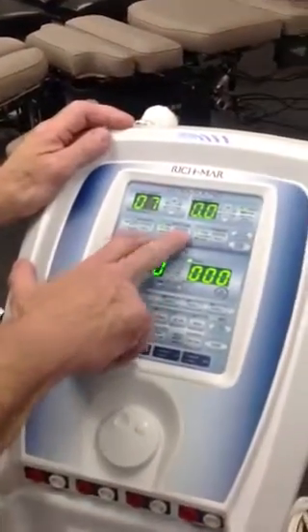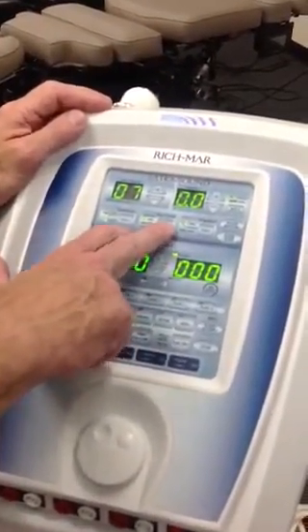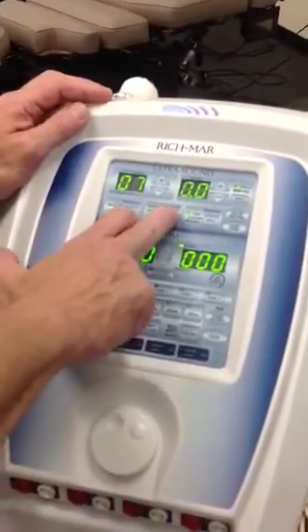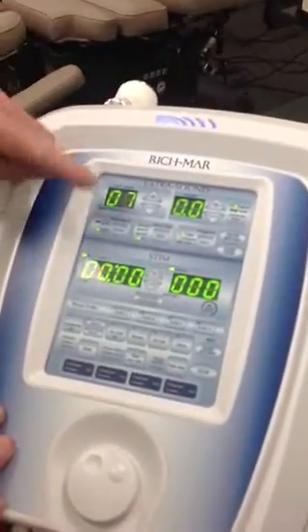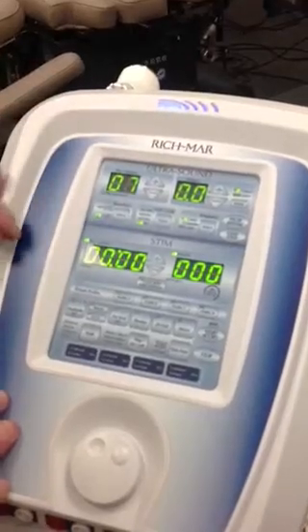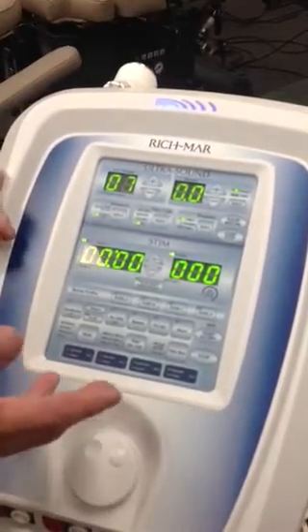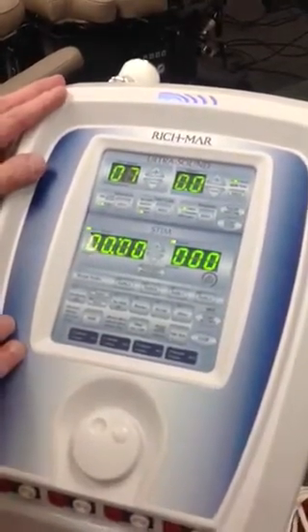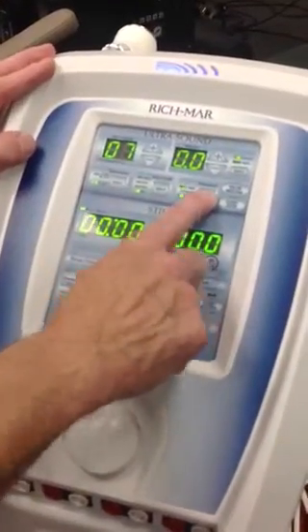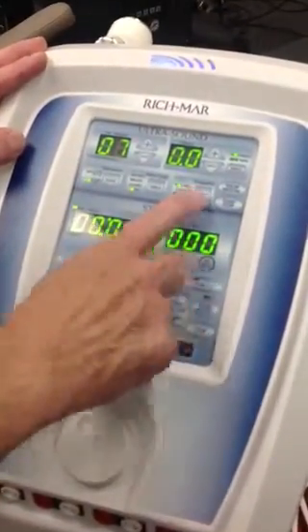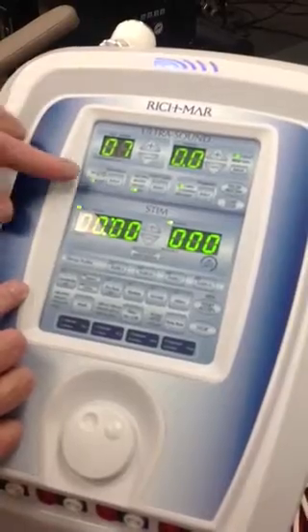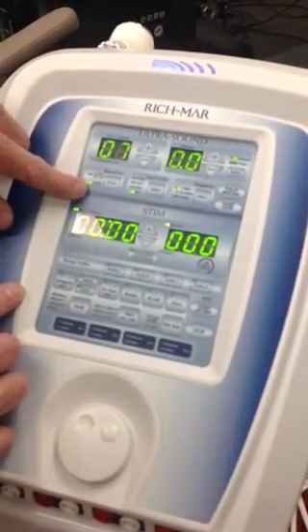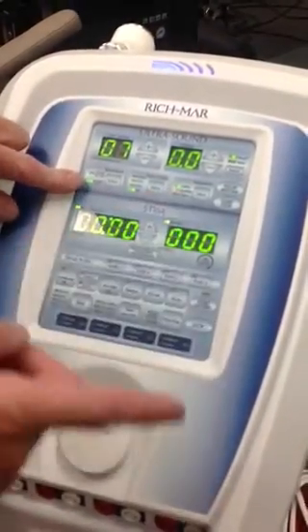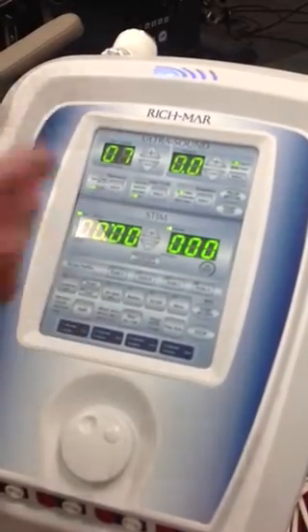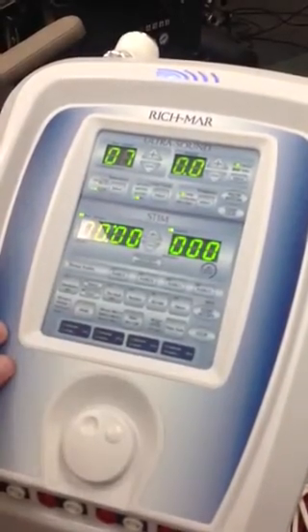Okay? Then we have our duty factor, which is 100, 50, 20, and 10. When it's 50, 20, or 10, an example is 20%, it's 20% on and 80% off. Okay, then we have our frequency, which is 1 or 3. In the ultrasound option, if you choose to get the ultrasound head, you can get a pass at 1 and a pass at 3, which gives you both deep and superficial.